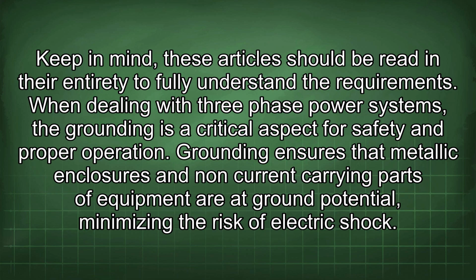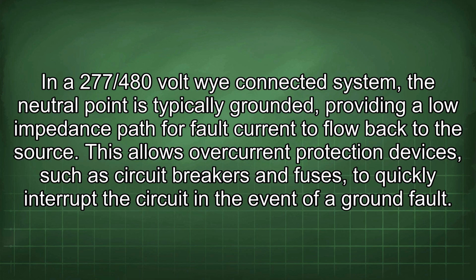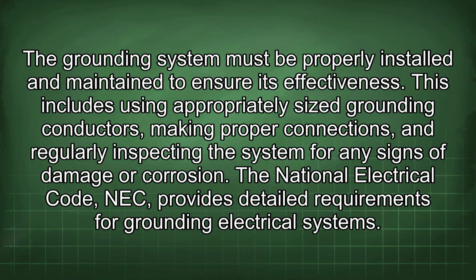When dealing with three-phase power systems, the grounding is a critical aspect for safety and proper operation. Grounding ensures that metallic enclosures and non-current carrying parts of equipment are at ground potential, minimizing the risk of electric shock. In a 277/480 volt Y-connected system, the neutral point is typically grounded, providing a low impedance path for fault current to flow back to the source. This allows overcurrent protection devices, such as circuit breakers and fuses, to quickly interrupt the circuit in the event of a ground fault. The grounding system must be properly installed and maintained to ensure its effectiveness.